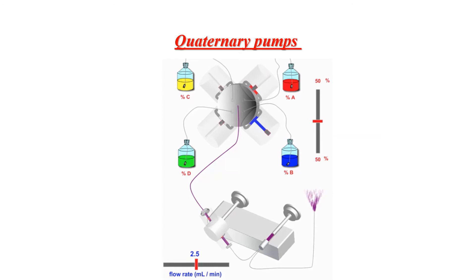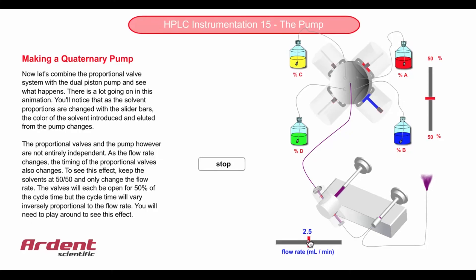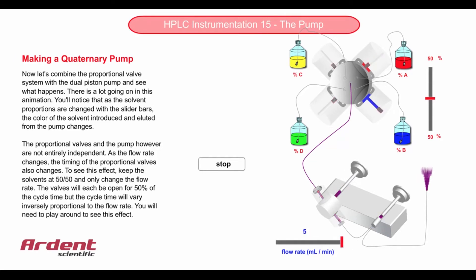This is the complete design of the quaternary pump. As we can see, there is only one dual piston pump, and the mixing chamber contains a proportionating valve. We can see one valve for each solvent, which controls the ratio of the solvents reaching the column. To understand how the proportionating valve controls the solvent ratio, let's look at some examples.